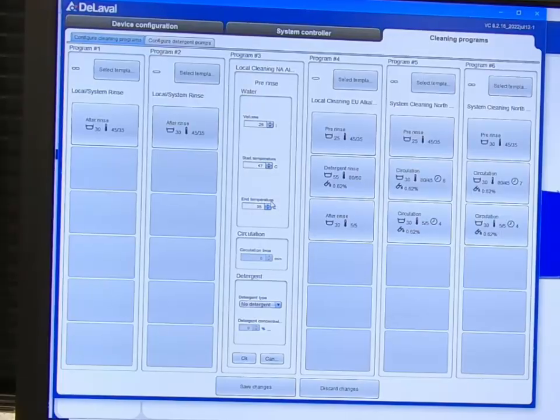You should not adjust the end, i.e. low temperature limit for the rinse. Leave that number alone. Make your adjustments only with the high limit. Do not set the high temperature right next to the end temperature or low limit. If you do that, the hot and cold water valves will cycle on and off repeatedly, trying to chase the temperature, and those repeated on-off cycles of the water taps will burn the valves out.